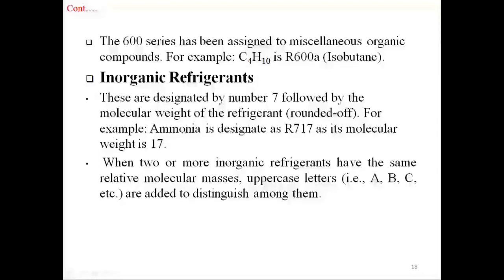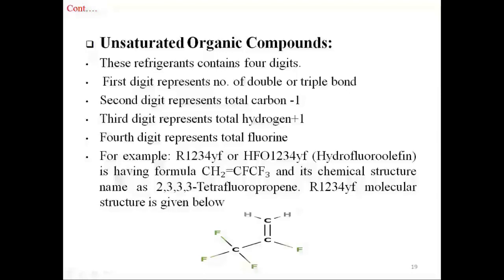When two or more inorganic compounds have the same relative molecular mass, uppercase letters A, B, C are added to them. Unsaturated organic compounds contain four digits: the first digit represents the number of double or triple bonds, the second digit represents total carbon minus one, the third digit represents total hydrogen plus one, and the fourth digit represents total fluorine. For example, R1234YF (also called HFO-1234YF; HFO means hydrofluoroolefin) has the formula CH₂=CFCF₃ and its chemical structure name is 2,3,3,3-tetrafluoropropene.